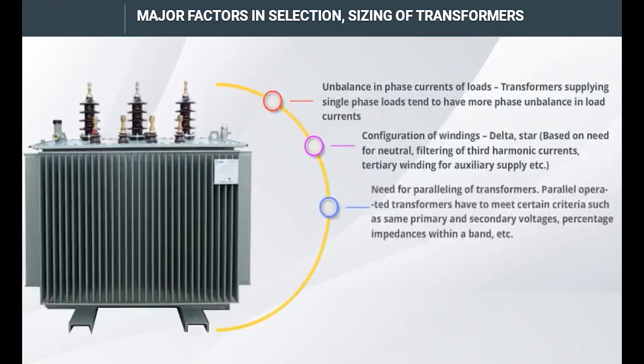The need for paralleling of transformers must be assessed. Parallel operated transformers have to meet certain criteria, such as having the same primary and secondary voltages and percentage impedances within a defined band.